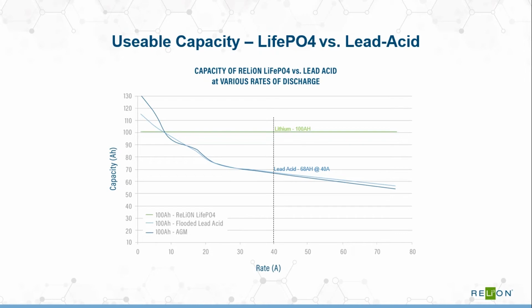amp hours, regardless of how quickly you take that energy out. So whether you discharge at 1 amp or 70 amps, you still have 100 amp hours, which isn't true with our lead acid battery, where you have only 68 amp hours at that 40 amp rate, and it declines as you go further. So to prevent irreparable damage, lead acid batteries shouldn't be discharged below 50% of their capacity. So that's where that 68 amp hours, if you're discharging at a high rate, 50%, you reach your limit a lot sooner.